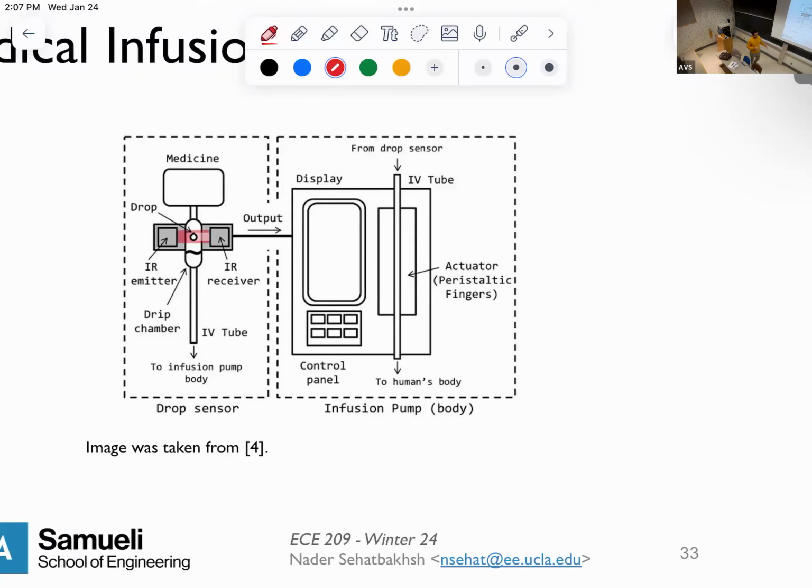So typically there is some form of infusion pump or some circuitry that controls this. Typically it also has some form of display to send and receive commands. The idea here is that the system will monitor this specifically. The monitoring system itself is fairly straightforward. It's two IR sensors, visual sensors.